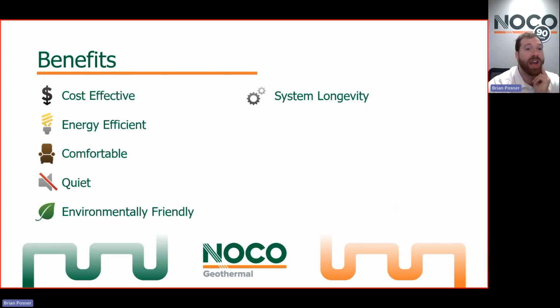System longevity. Again, because of no combustion, no combustion chamber, no heat exchanger to crack. You're not putting that intense burning of fuels inside a compartment. You're not doing that inside your home anymore. Well, that means the system's going to last a lot longer. There's a lot less wear and tear on it. You're likely to see your geothermal system last for easily over 30 years, rather than current furnaces and boilers that seem to be kicking out at around 15, 20 years.